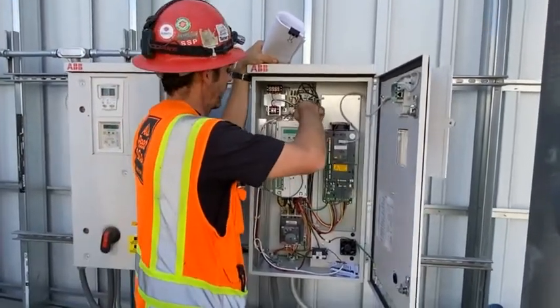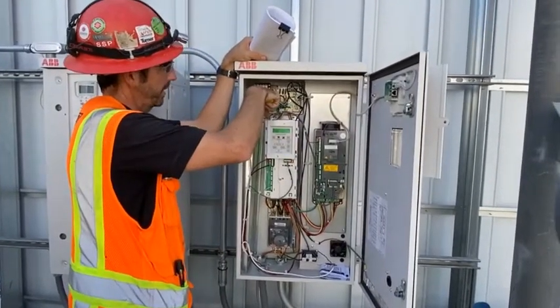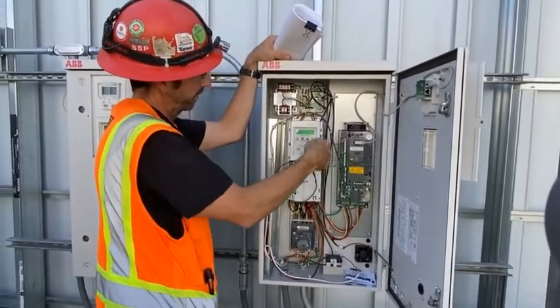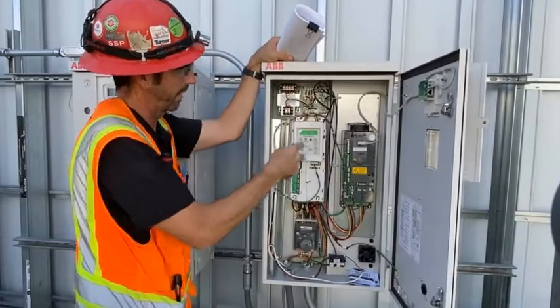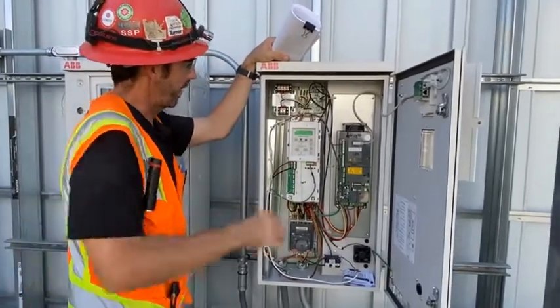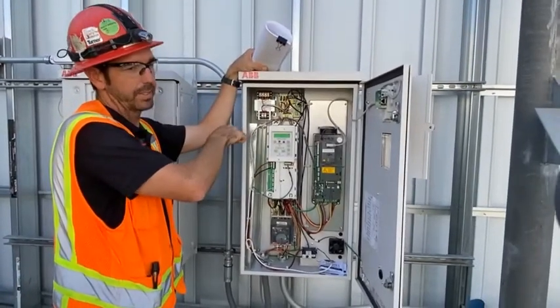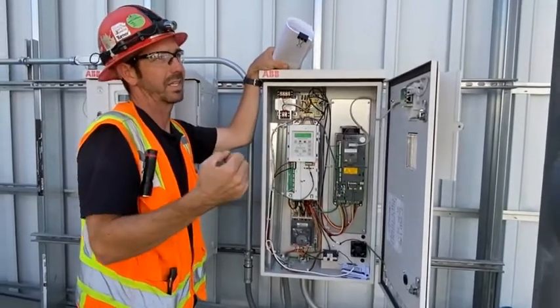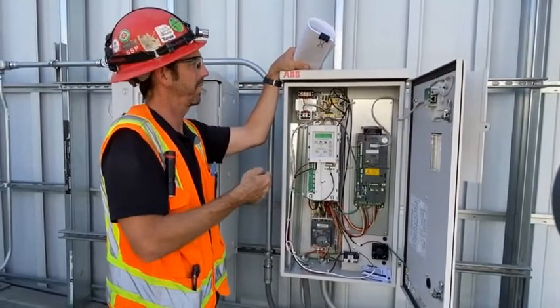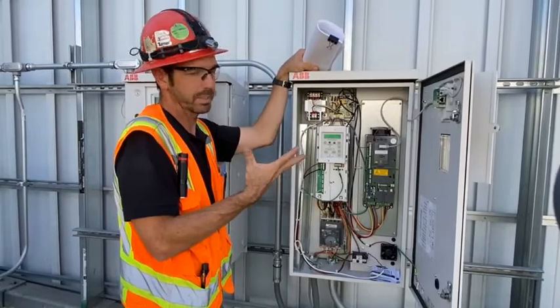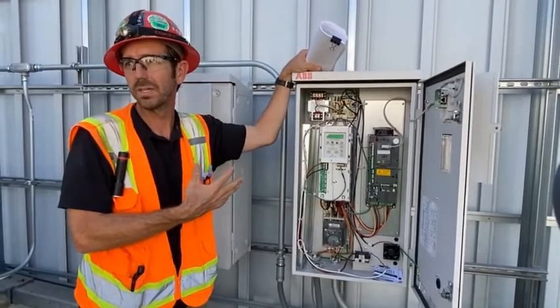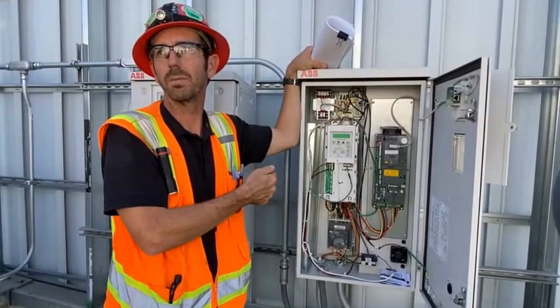You can undo the fan connection up here and the communication link up here, and then there's 4 snap screws that this whole Eclipse bypass panel will come off. And that way you can get to the contactors behind it to check the tightness of all the lugs. As things heat up and cool down, especially being up here, things expanding and contracting can become loose, and a loose wire will create nothing but problems for a VFD.